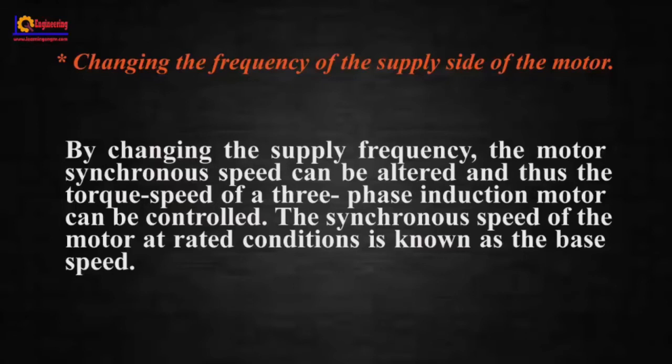For changing the frequency of the supply to the motor, by changing the supply frequency, the motor synchronous speed can be altered and thus the speed of the three-phase induction motor can be controlled. The synchronous speed of the motor at rated condition is known as the base speed. And the second part is speed control of the induction motor on the rotor side.